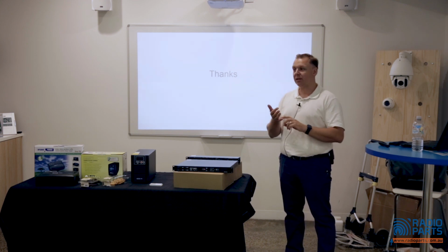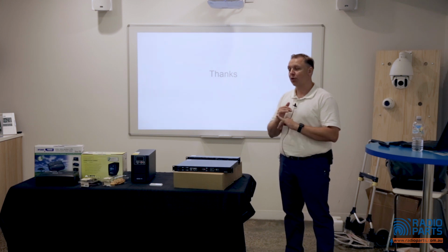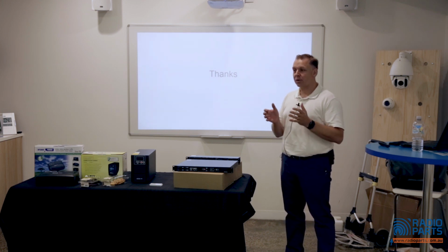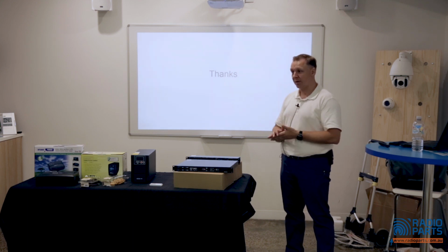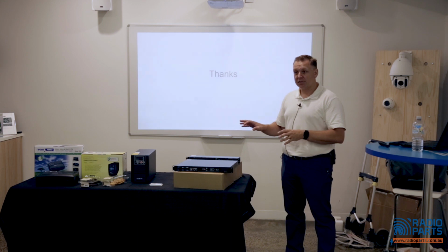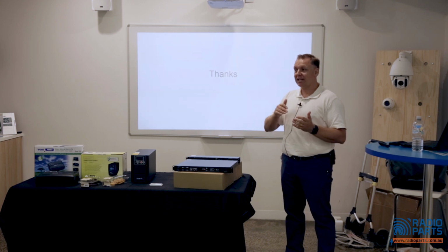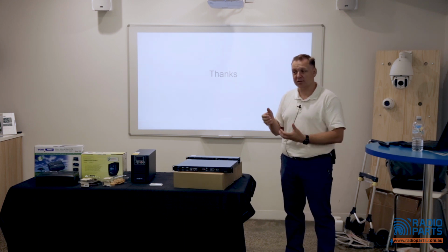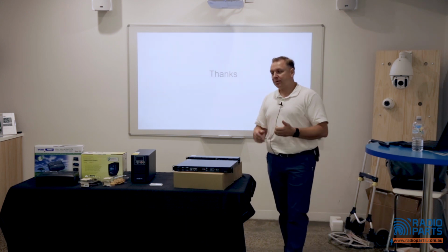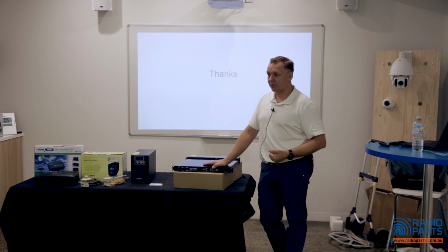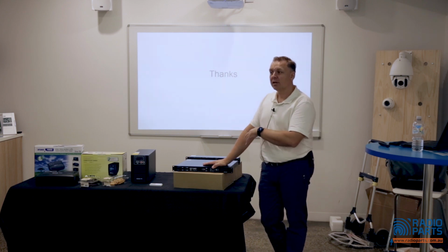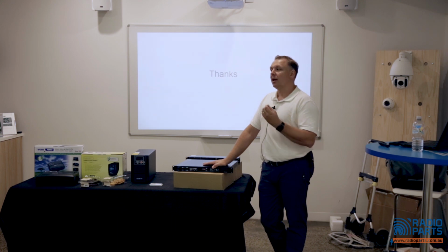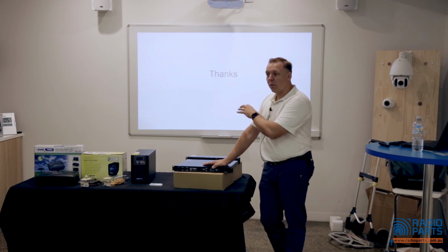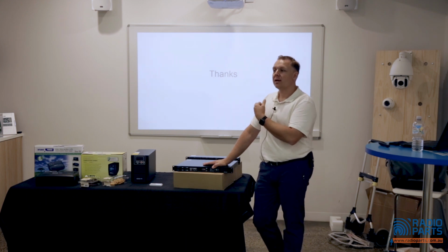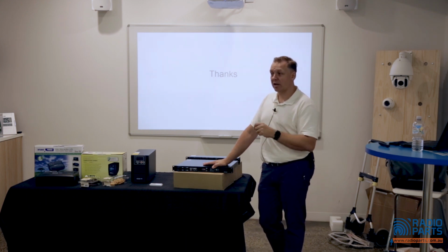The short version, yes, it's being looked at. I quoted one just recently. It's horrendously expensive, so the only time it's worth considering at the moment is really high temp applications. Typically lead acid battery design temperature is 25 degrees ambient, and for every 10 degrees you go above that, you half the battery life. That's actually a pretty big difference. In this particular application, it was still cheaper for them to change the batteries every 2 years for the life of the UPS than go with lithium batteries. On top of that, no one that does a UPS, at least that I'm aware of, has a charger built in that is designed to charge a lithium battery properly.